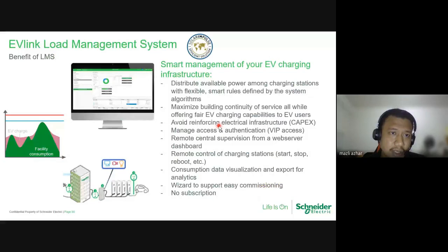So for load management systems, not just Schneider, any brand will have this type of technology, which helps to distribute available power evenly among charging stations, where the user can create smart rules. You can maximize the continuity of service in the whole building. Take for example a building with 10 EV chargers. When all 10 are occupied, if they don't have a management system, it will create a spike in the electricity demand.